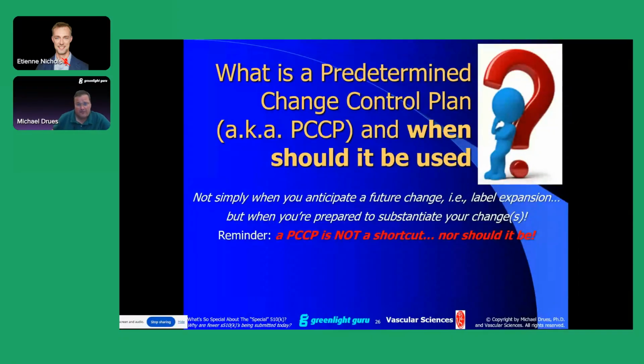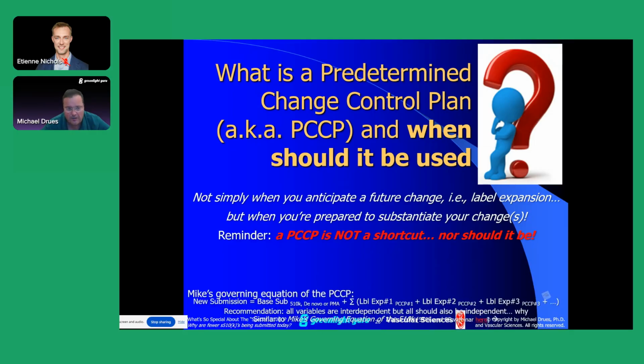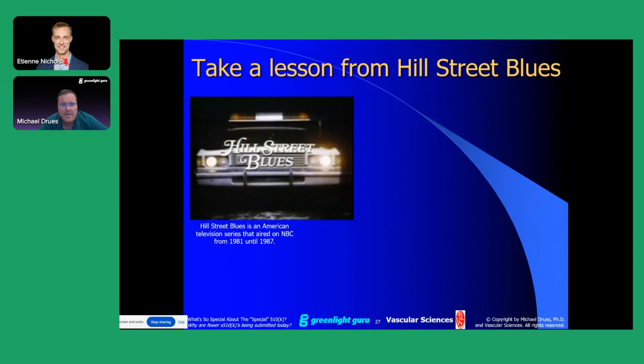So what is the PCCP and when should it be used? If you anticipate wanting to make a change to your device in the future, like a label expansion, and when you're prepared to substantiate that change. But remember, a PCCP is not a shortcut, nor should it be. So if we're going to take a lesson, I said a moment ago, we should be very careful here about how we handle changes, because this gets a lot of companies into a lot of trouble. As I said, it's the single biggest reason why companies get in trouble with the FDA upon manufacturing inspections.